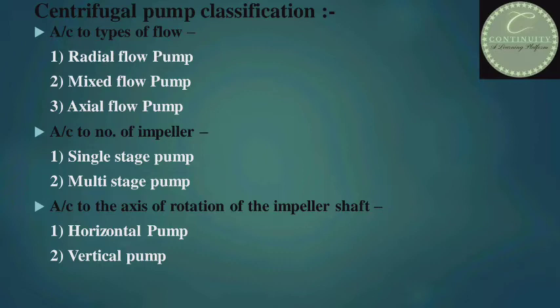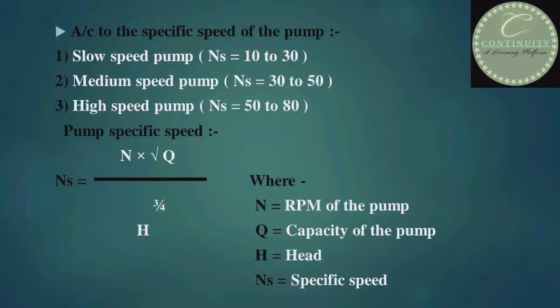According to specific speed: first, slow speed pump — its specific speed lies between 10 to 30; second, medium speed pump — its specific speed lies between 30 to 50; and third, high speed pump — its specific speed lies between 50 to 80. The formula for specific speed is: N_s = N × √Q / H^(3/4), where N is the RPM of the pump, Q is the capacity or discharge, and H is the head developed by the pump.